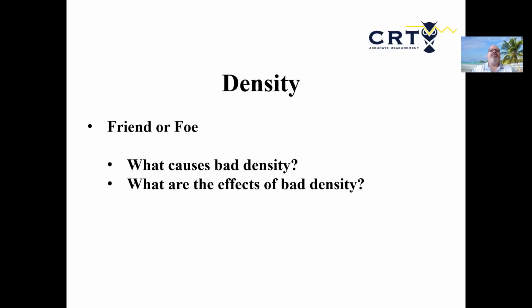Density, I'm just going to mention it real quick. In liquids, one of the biggest effects of our volumetric corrections is density. I call it a friend or a foe, but if your density is not right, if you're not calibrating it, not verifying it, and you don't know what density is when programming flow computers, you need to find out, because density is the basis of your corrections in the flow computers, along with temperature and pressure. It has a huge impact on the volumes you're billing for.